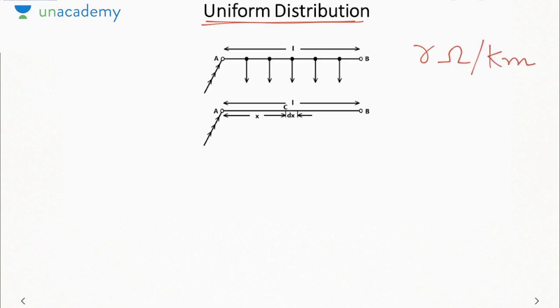Current being drawn is I ampere per kilometer. So we show current being drawn continuously by the loads from the line, and the total length of the line is L.